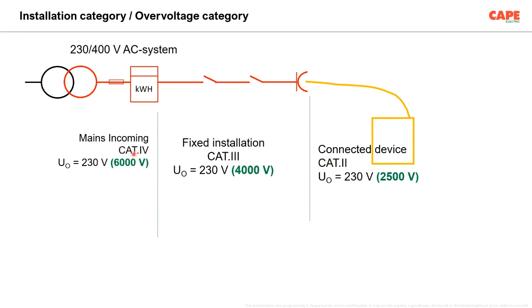This means the electrical appliance used at the origin of installation or point of commencement of supply must be of category 4. Example, a 230 volt equipment, 230 volt between line to neutral equipment, must be able to withstand 6 kV, 6000 volt voltage impulse withstand. Means a surge voltage of up to 6 kV, these equipment are supposed to withstand.